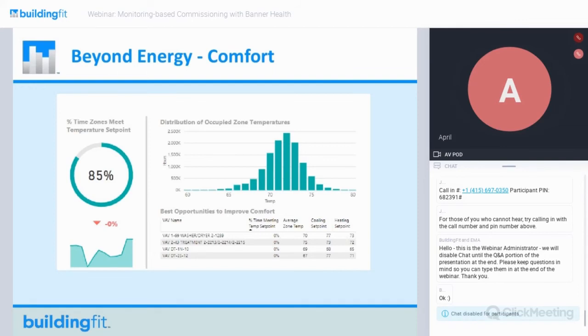In this report on the screen, that big 85% in the circle is the percent of time the zones are meeting temperature set point. We've also tried to include a very actionable table called Best Opportunities to Improve Comfort, showing the top zones that are not performing well as far as comfort goes—in this case, zones not meeting their temperature set point at all, ever. By working off this list together with the facility to get these zones resolved, the hope is that the 85% number can go up, that KPI can go up, and they can move on to other things instead of spending so much time on comfort issues.